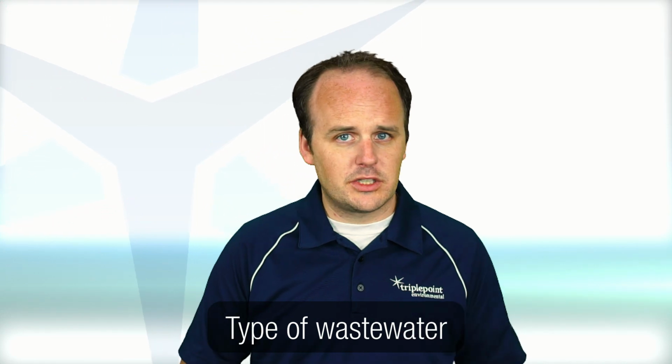Are you dealing with industrial wastewater, municipal wastewater? If it's industrial, there are thousands of different types of industrial wastewater, and that ultimately informs our field transfer efficiency equation, because if it's pulp and paper wastewater versus municipal wastewater, we need to put more air in the water in order to transfer oxygen to water than we do in municipal, because that bubble is not as effective in dirtier water than it is in cleaner water on the municipal side.